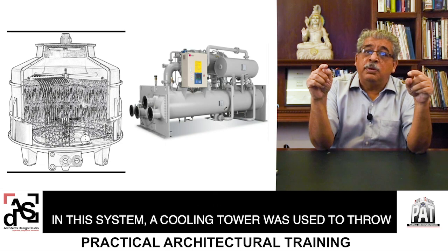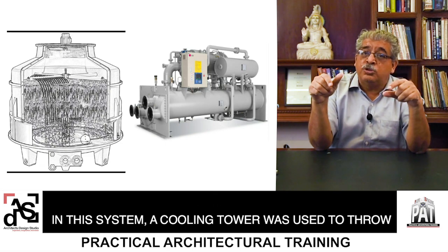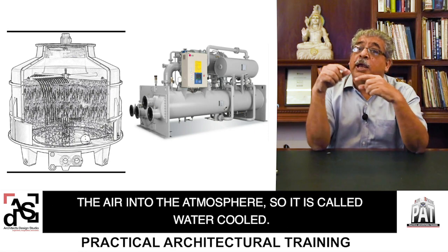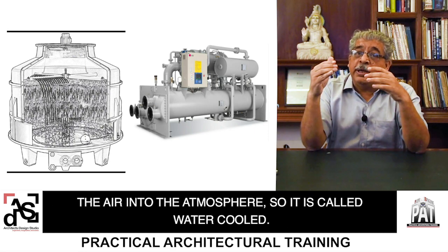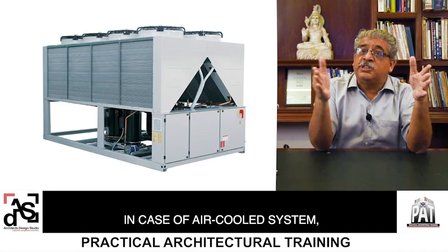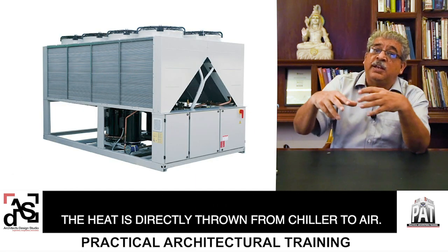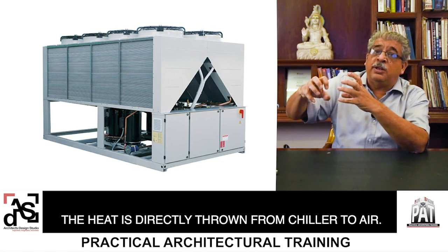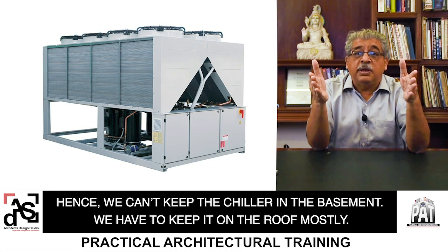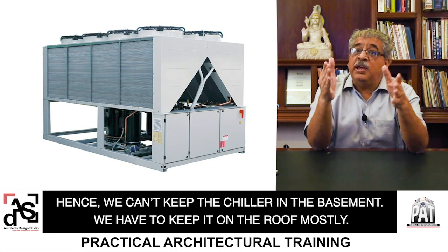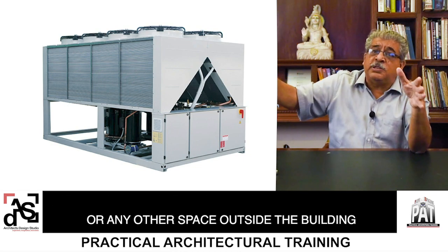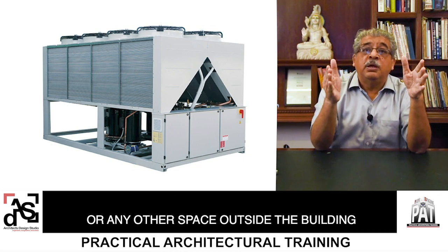In this system, a cooling tower was used to throw the heat into the atmosphere. So, it is called water cooled. In case of air cooled system, the heat is directly thrown from the chiller into the air. Hence, we can't keep the chiller in the basement. We have to keep it on the roof mostly, or any other space outside the building.